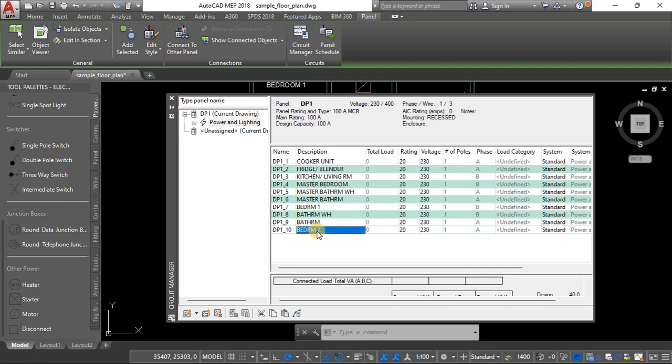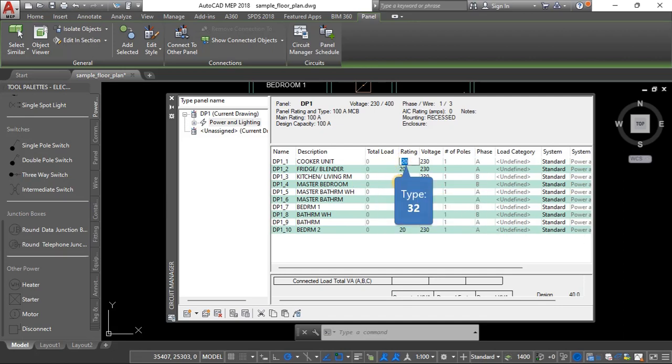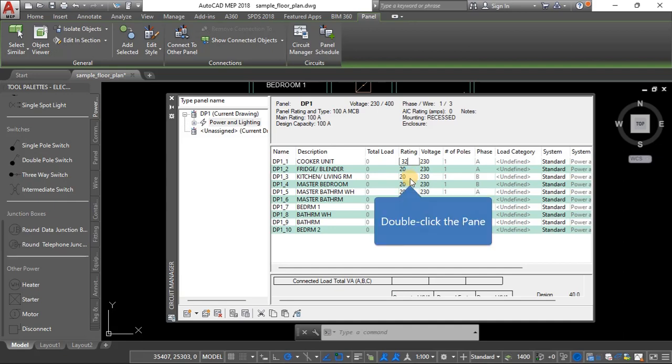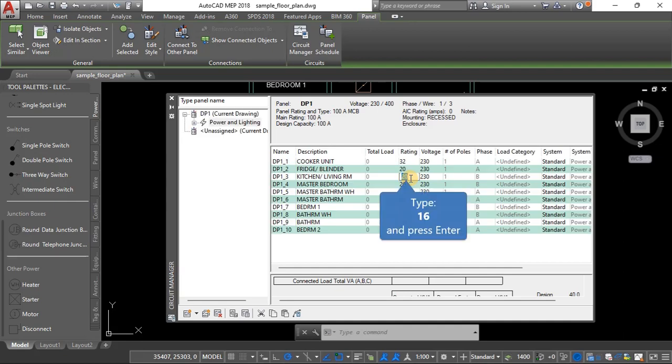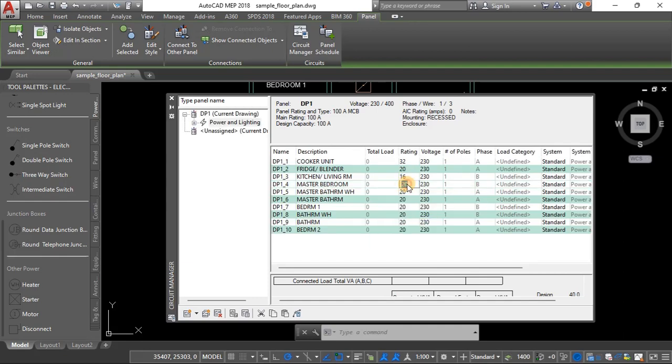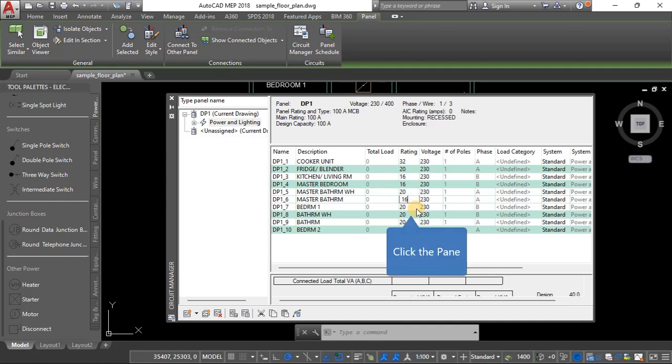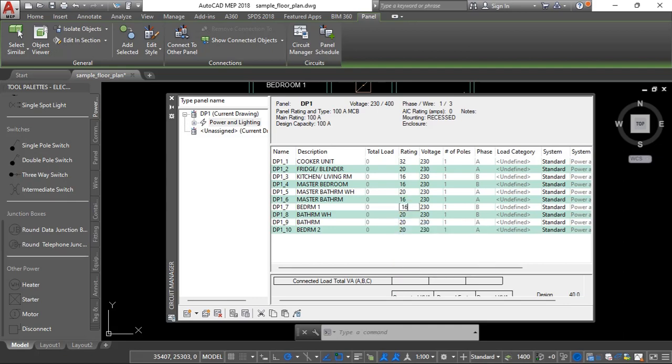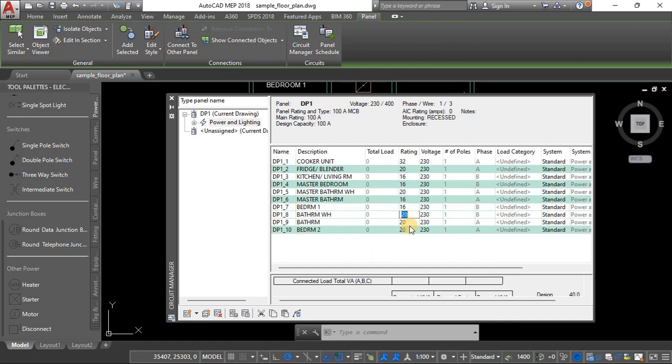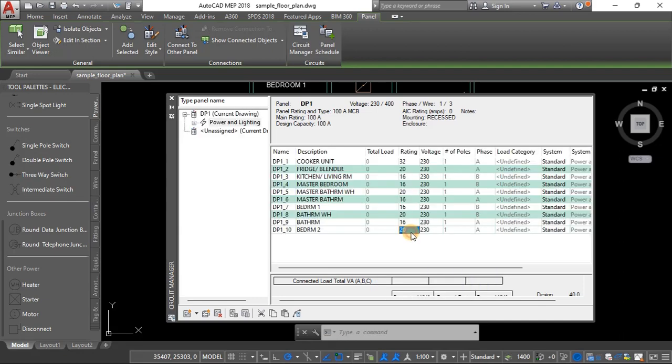Okay, okay so those are the 10 circuits. So the cooker unit, cooker unit over here, we should have a rating of 32 amp for the breaker. Fridge blender let's leave it at 20. Living room kitchen I'll assign it 16, and master bedroom I'll give it 16. Bathroom water heater I'll leave it as 20. Master bathroom I'll just give it 16. Bedroom one 16. This bathroom water heater 20. The bathroom 16, the bedroom two should also have 16.